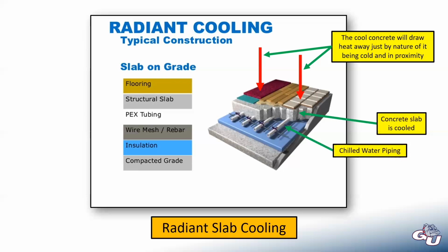We have this at our McKinstry building, and it seems to work pretty well. The only downside is you have to be careful about cracking the concrete, because concrete is a pretty good thermal battery, and if you impart large temperature swings in a short amount of time, you can end up cracking it. That's especially true if you have a parallel piping system also running hot water, which is something else we have at our building. In the winter months, we heat this slab with hot water for a radiant heating effect, and in the summer, we run chilled water for a radiant cooling effect.